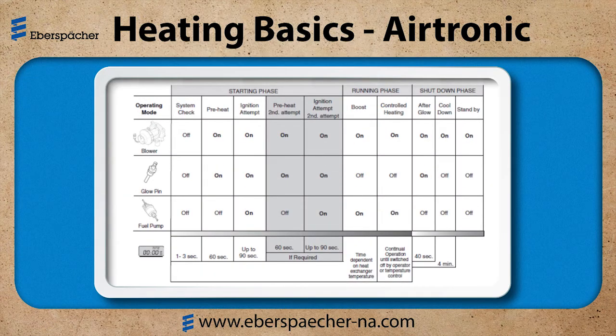Now we'll look at the heater operation. There's a starting phase, a running phase, and a shutdown phase. The important thing here is the timeline associated with each. Once I activate my heater, I do a quick system check. I'm looking at the blower motor, glow pin, fuel metering pump, and the safety sensors. This takes about 3 seconds. Then I go into my first preheat, which is 60 seconds. Then my first ignition attempt, up to 90 seconds. If the heater does not start at this point of time, I will go into a second preheat of 60 seconds, and then a second ignition attempt up to 90 seconds.